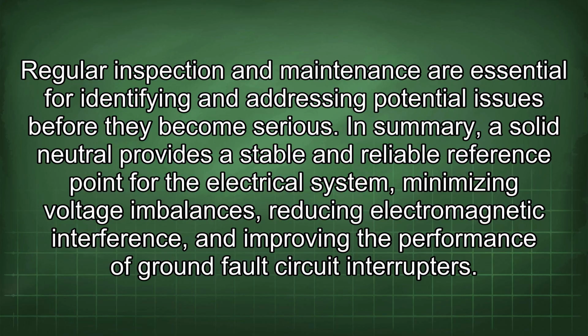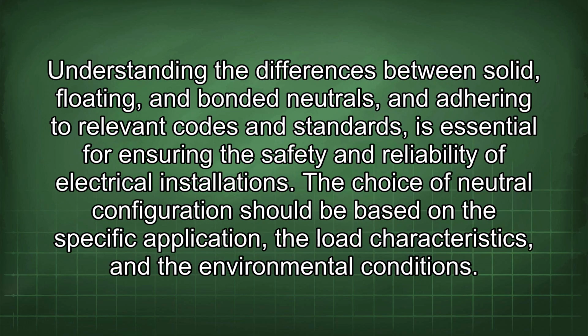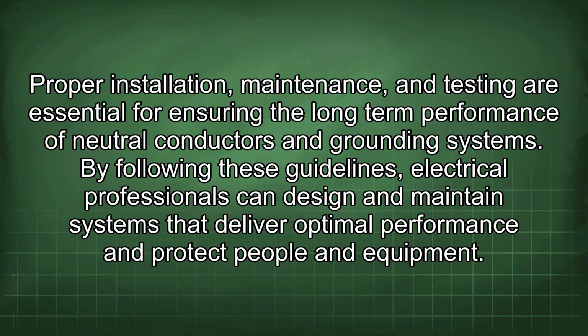In summary, a solid neutral provides a stable and reliable reference point for the electrical system, minimizing voltage imbalances, reducing electromagnetic interference, and improving the performance of ground fault circuit interrupters. Understanding the differences between solid, floating, and bonded neutrals, and adhering to relevant codes and standards is essential for ensuring the safety and reliability of electrical installations. The choice of neutral configuration should be based on the specific application, the load characteristics, and the environmental conditions. Proper installation, maintenance, and testing are essential for ensuring the long-term performance of neutral conductors and grounding systems. By following these guidelines, electrical professionals can design and maintain systems that deliver optimal performance and protect people and equipment.